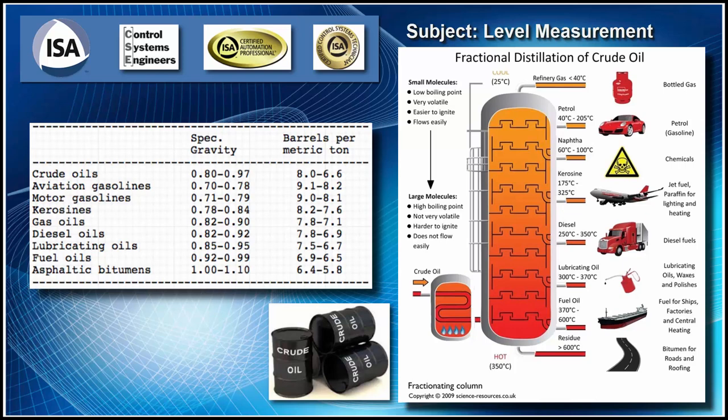So you remember from fluids, we said specific gravity is the ratio of a liquid to water at 60 degrees. And for gas, specific gravity is the ratio of a gas or vapor to air at 60 degrees. And so the specific gravity sets our weight. Remember, these molecules move around, and we have density, which is mass per unit volume, and we take our mass times acceleration of gravity and we get force per unit volume. So this is weight per volume, and we call this density. Water would be like 62.4 pounds per cubic foot. So we take our crude oil per cubic foot over water, or gasoline per cubic foot over water, and this ratio is called its specific gravity. And this is how we adjust our water column when we calibrate these transmitters to measure the height.